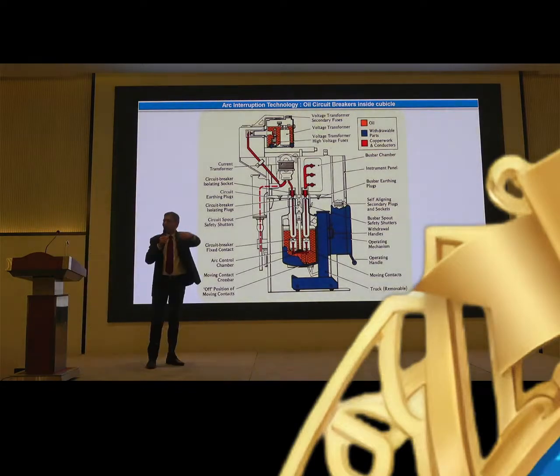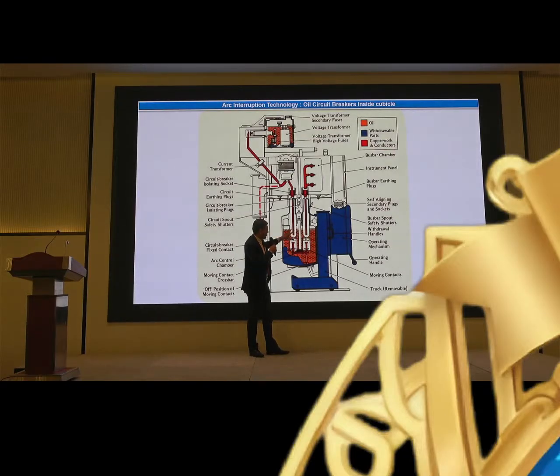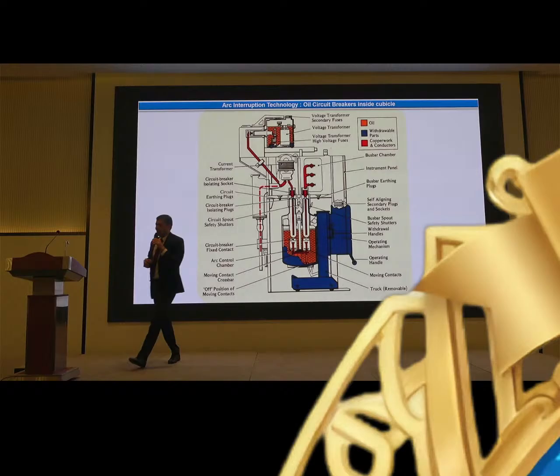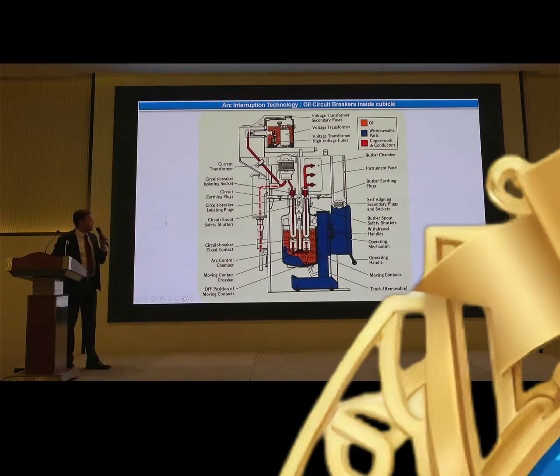And these switches are mounted on the wall. Why? Because you don't have to maintain them. But these breakers had a lot of mechanism, a lot of moving parts. So you had a fixed switch and a movable switch, to take it out and maintain it. So this is the cubicle. This is the bus bar, which gives current to this breaker. It comes here, it goes to the current transformer, voltage transformer, to the cable. It goes to the transformer and from there to your home or industry.